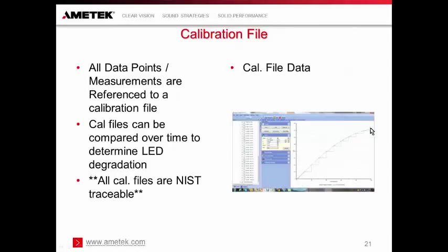So the curved line represents the software control, and the step line represents the hardware control. So we have two methods of calibration. But now we have this calibration curve, we know what the output is in terms of milliwatts per square centimeter as a function of drive power of the LED. So all data points now are referenced to this calibration file. You cannot run an experiment without a calibration file.